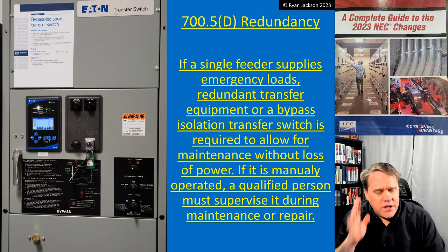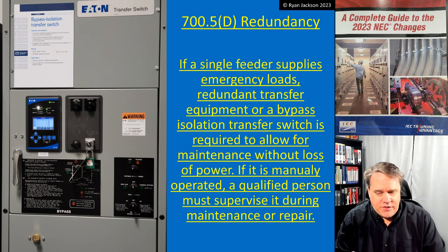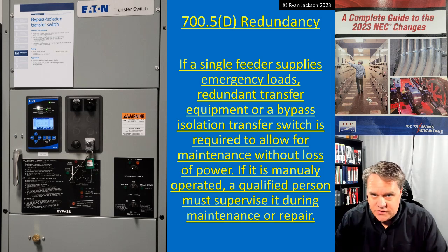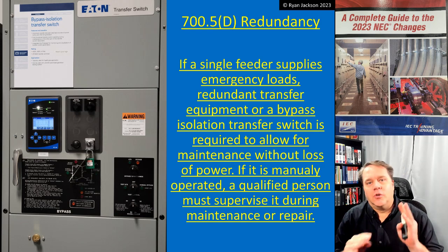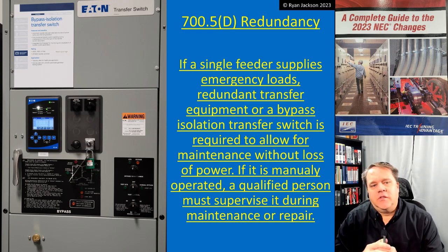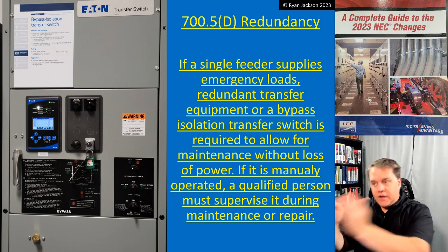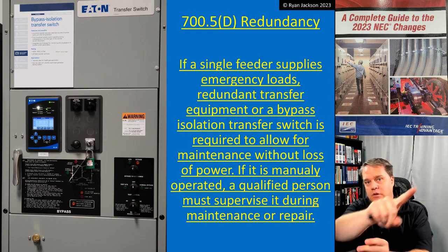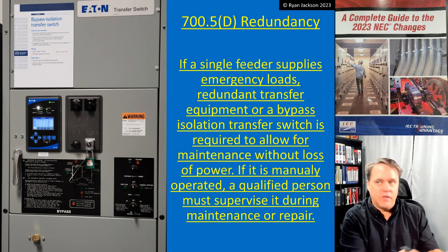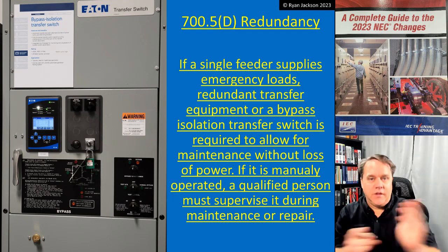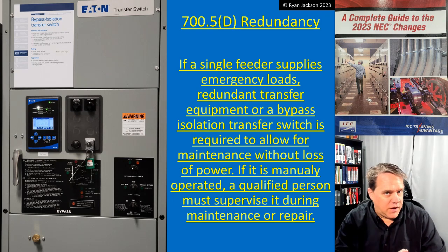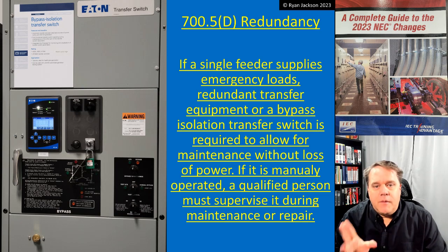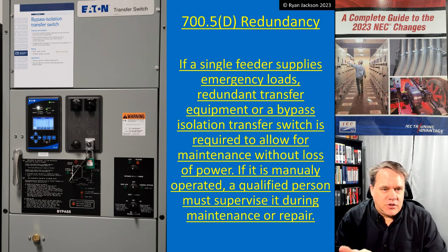We need people to maintain things and we need the emergency system to remain operational while we're doing it. So how do we do both at the same time? We either install a second transfer switch — use one while maintaining the other — or if we don't want to buy two, buy a bypass isolation transfer switch.